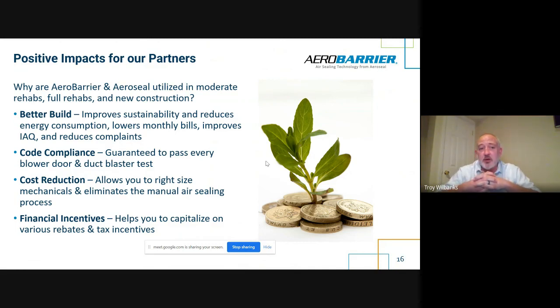Reduction in cost of the build, if it's a total rehab, right? Taking a look at, instead of going for the 5 air change requirement, what does it look like if we come in at 2 air change? Can we take a half ton to a ton off the equipment? We definitely can.